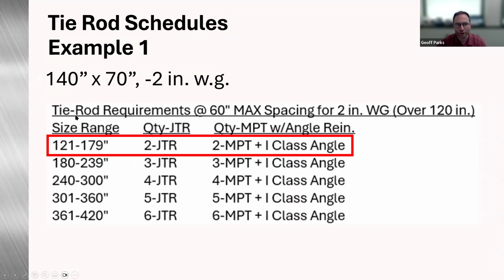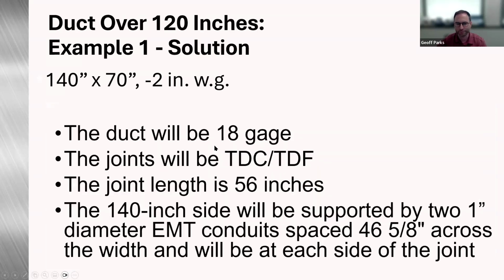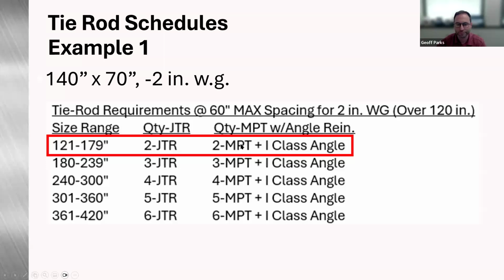So if we came to the tie rod requirements for 2-inch water gauge, duct over 120, and we came to our size range, so we're 140, this schedule here is telling us we need 2 JTRs at the joints, and then, wow, my computer's touchy, sorry about that, it keeps jumping ahead. Then we need 2 mid-panel tie rods plus the I-class angle.